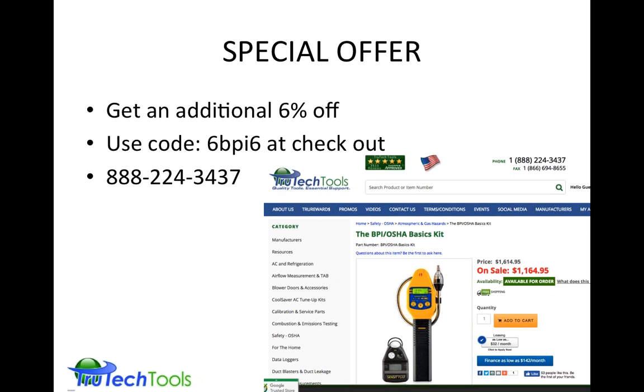How often is factory calibration required? That's usually something that the manufacturer will specify. Typically, it's annual calibration. Some of the products you can actually buy cal kits, you can get replacement sensors, or you can use the manufacturer or a third party. TruTech Tools does provide the third party service.